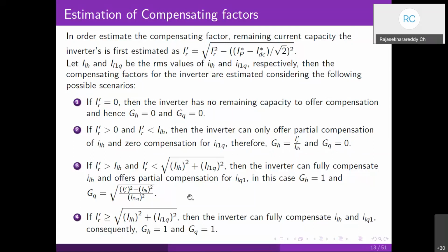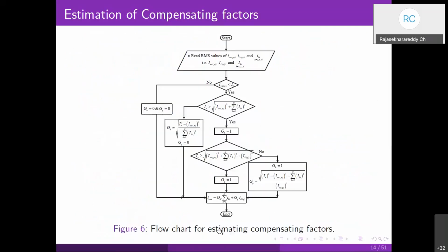Then the third case is where the inverter's remaining current capacity is more than the harmonic current value but less than the combined harmonic and reactive currents. In that case, the inverter can fully compensate the harmonic currents but can only partially compensate the reactive current. So this is how we calculate GQ, and we set GH equal to 1 in this case. Then the final case is where the remaining current capacity is enough to compensate both the reactive and harmonic currents together. In that case, we make GH and GQ equal to 1. This is how we approach it. Then this is the flow chart.